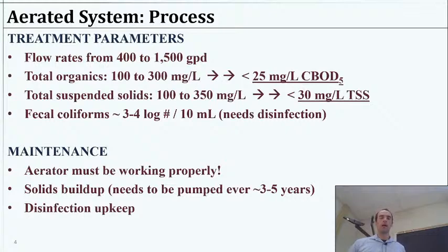The goal and target performance of an aerated system like this would be to bring that down to about 25 milligrams per liter of carbonaceous biological oxygen demand, the BOD5 measurement.